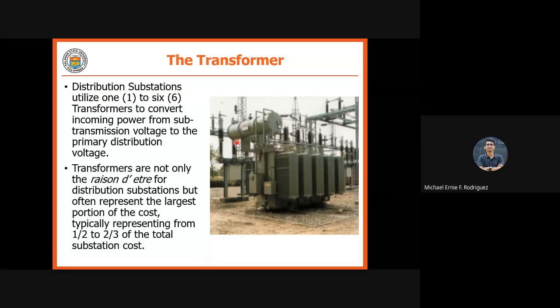So, transformers are not the only reason for this. It often represents the largest portion of the cost. Napakamahal ng transformer na yan. So, usually that is 1/2 to 2/3 of the total substation cost. So, ganun kamahal yung ating transformer. So, kung yung high voltage side buswork is 1/4 to 1/3 of the total substation cost, ito naman is 1/2 to 2/3 of the total substation cost. Ganun siya kamahal.